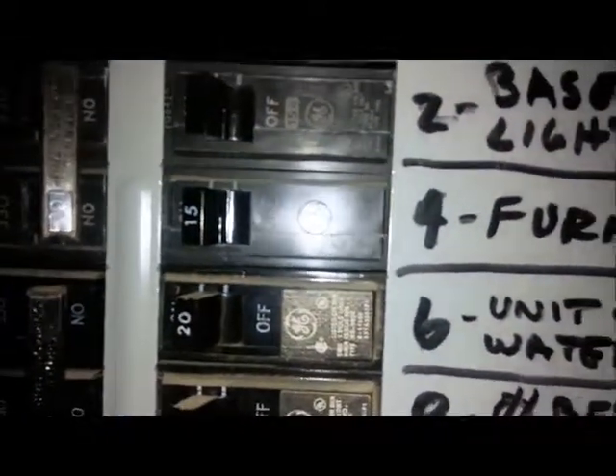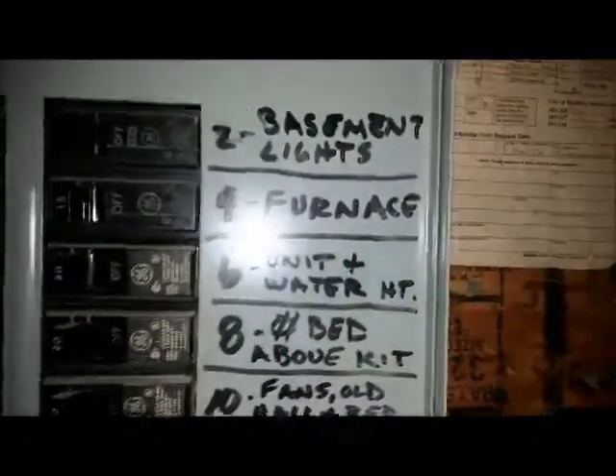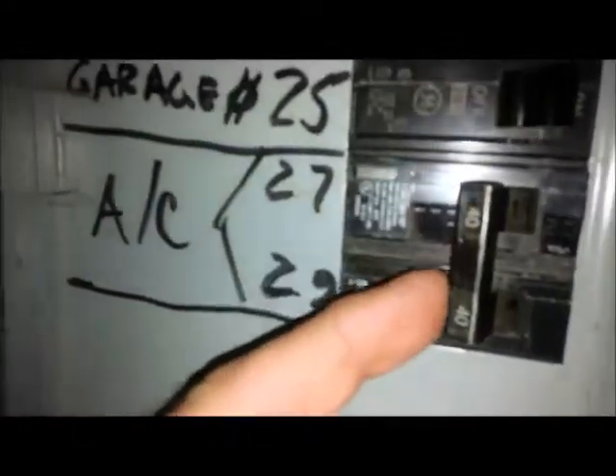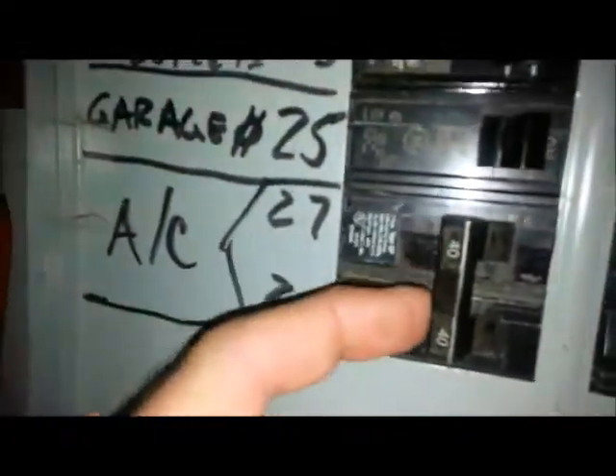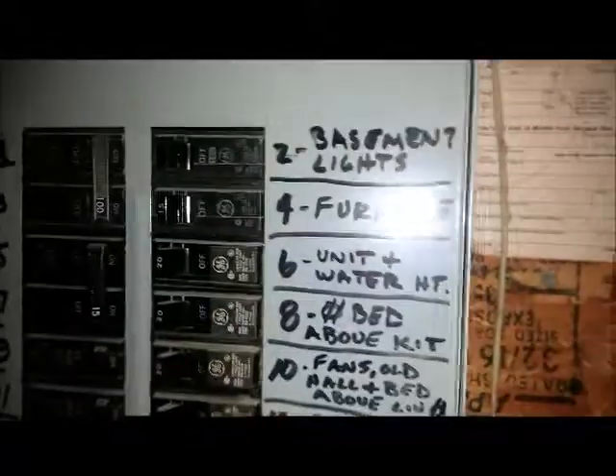And that is going to be a single pole 15 amp breaker. Typically your air conditioner is going to be a double pole, similar to that. Double pole means it's taking 110 volts off each leg coming into the house. So you've got 240 for the AC and 120 volts for the furnace. So once you verify you have power, which basically this simulates our breaker being turned on.